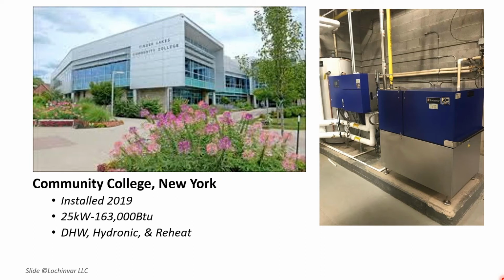What they decided to do overnight was divert the 163,000 BTUs into their heating loop, just putting light heat throughout the building. Unintentionally, this eliminated their condensate issues on the interior windows. The 25 kW was easily absorbed because they had parking lot lights, hallway lights, and other areas with lighting maintained at night, so there was use for the power and no issues absorbing it. Again, the environmental benefit is a big issue with micro-cogeneration.